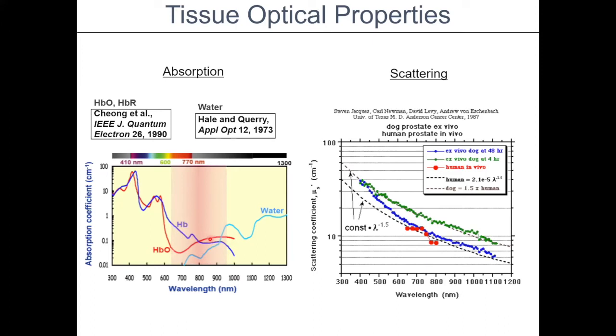And if you're doing cerebral measurements, the percentage of water in tissue doesn't vary that much, so you can make perhaps an assumption. If you're measuring other parts of tissue, you're right, you should really have an idea how much water you have. So at a minimum, you need another wavelength, preferably above 800 something nanometers. And it's kind of going from there.